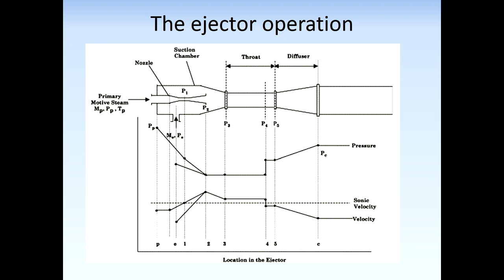The location of the shock wave depends on the back pressure from the condenser. Finally, the subsonic flow enters the diffuser and is compressed isentropically to pressure pc, which is between the generator and evaporator pressures. This is how an ejector operates.